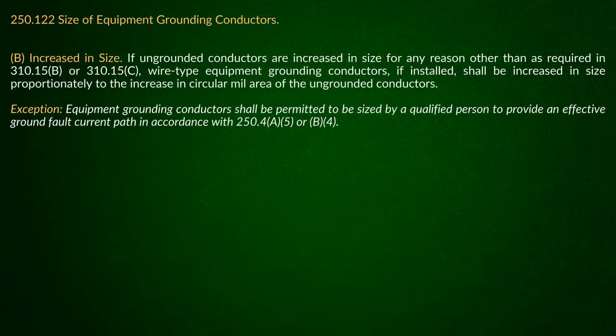And is that true or not? That's true. That's a good point, but at the same time, you have to keep in mind that if you're doing adjustment factors on that, and I know James is probably gonna cut me off on this one, but when you have adjustment factors in there, that's where you run into some of these problems with the equipment ground, because you're adjusting based off the 90-degree C column. All this kind of stuff with the equipment ground comes in, and I think that's where we get in these arguments.